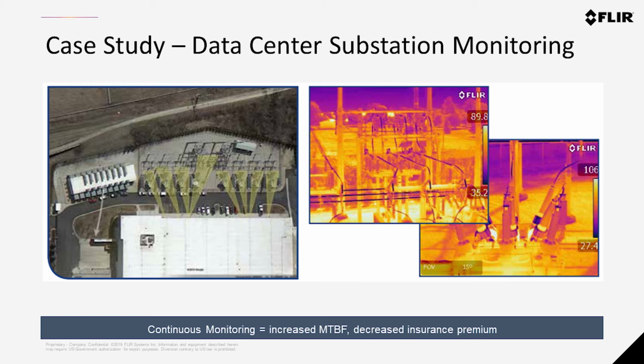I don't know exactly who this particular one was, but some data center operator installed a system of 8 cameras constantly viewing their high voltage supply from the utility. Even though they have good, robust standby power systems internally so they don't disrupt service for customers, they really never want to lose utility power in the first place. So they installed this more complicated system with continuous monitoring to make sure nothing leads to a failure in that substation. Again, the idea is to trend data over time, keep an eye on critical elements, and as soon as something trends in the wrong direction, you have time to plan and take corrective action.